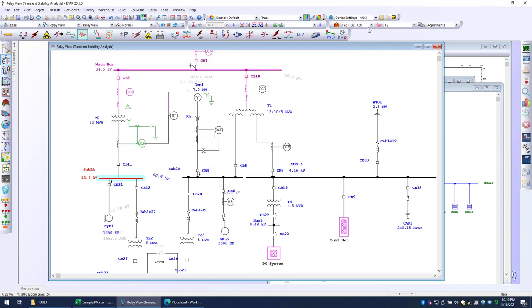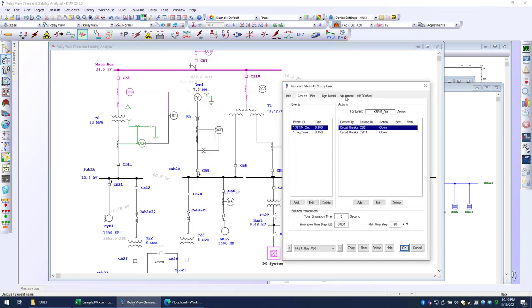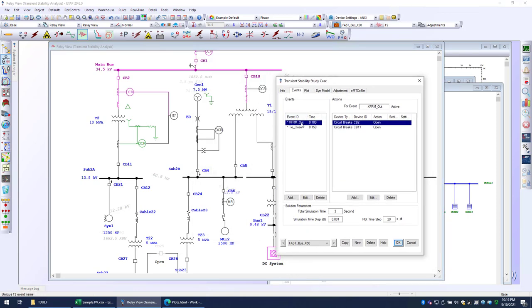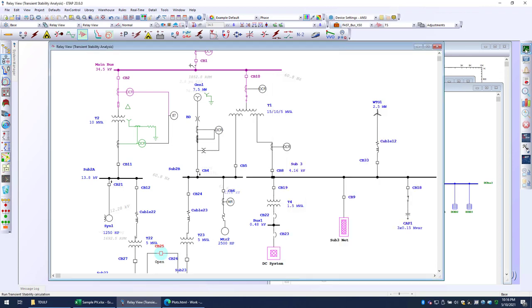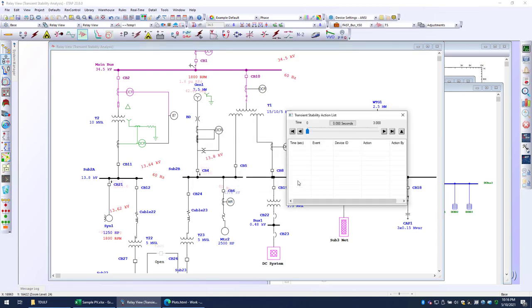So what I'm going to do is select the events. The events are as follows. At 100 milliseconds, we're going to open CB2. As you can see highlighted on the screen, we're going to open CB11. And then just 50 milliseconds later, so at 150 milliseconds, we're going to close that tie, CB25. So let's go ahead and perform this simulation.